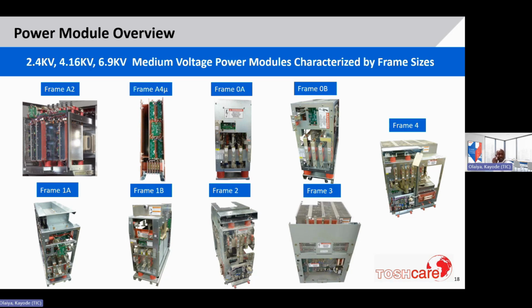Starting from the left, there's the frame 2, A2, which is the power module used in the 2.4 kV drive up to 500 horsepower. The A4 micro, that's a 4160 volt power module that goes up to 600 horsepower. We have the frame 0. You notice that there's an A and a B. And this is for the 4160 drive up to 1,000 horsepower.